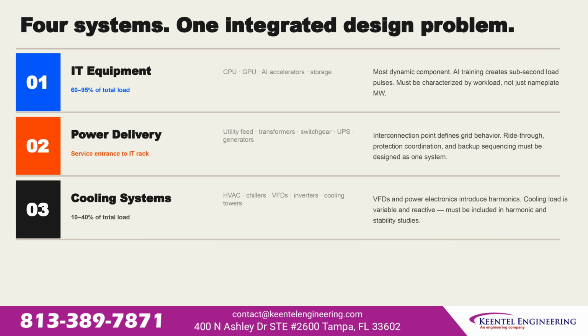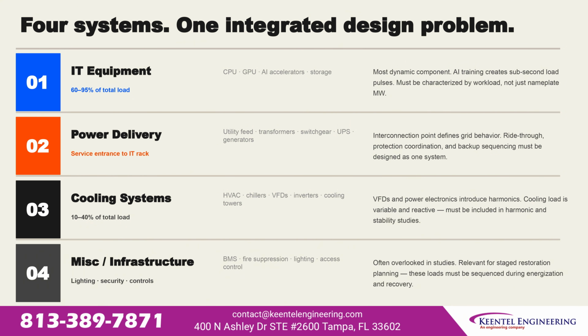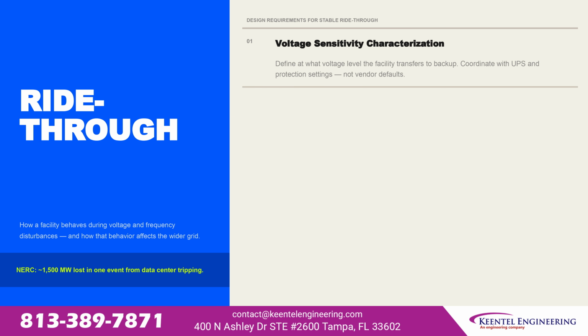3. Cooling, 10 to 40% of total load. VFDs and power electronics introduce harmonics. Cooling load is variable and reactive, and must be included in harmonic and stability studies. 4. Miscellaneous infrastructure: BMS, fire suppression, lighting, access control, often overlooked. Relevant for staged restoration planning and energization sequencing. Ride-through is how a facility behaves during voltage and frequency disturbances, and how that behavior affects the wider grid.